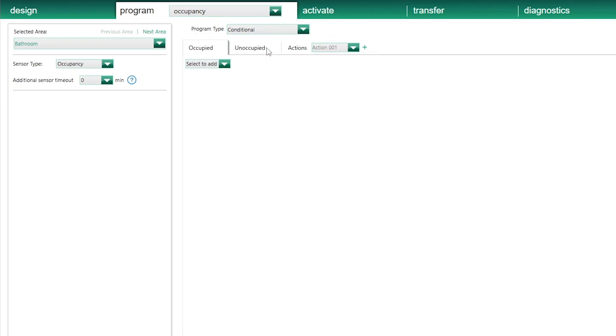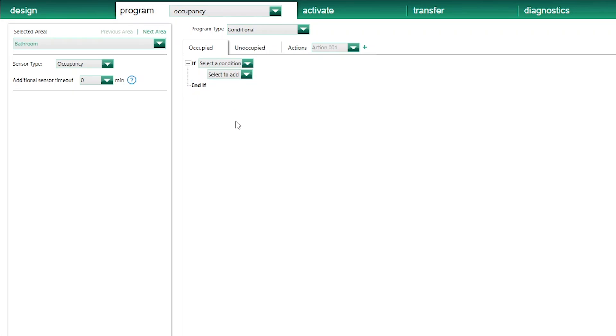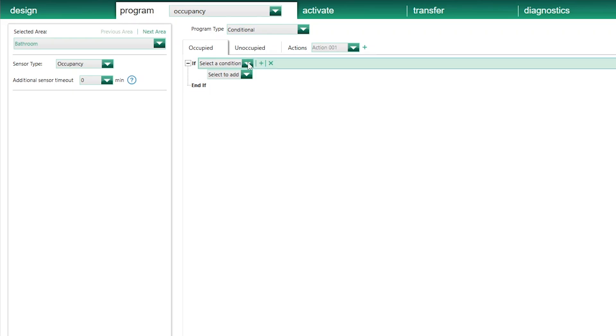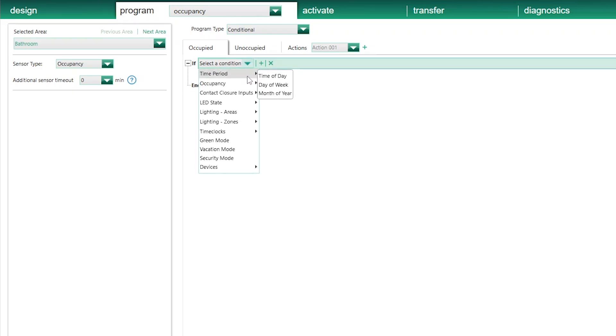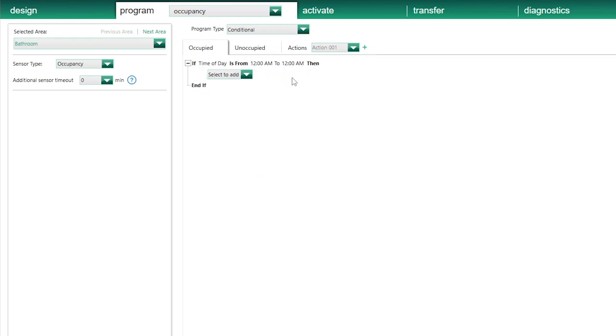The space underneath changes a bit. In the Occupied tab here, I'm going to program what I want to happen when someone enters the bathroom. First step: I select Add Condition. What condition would I like to check? Is it night time? In the If section, I select Time Period and then Time of Day. I will create a period of time I will consider to be night time for the operation of my bathroom light.